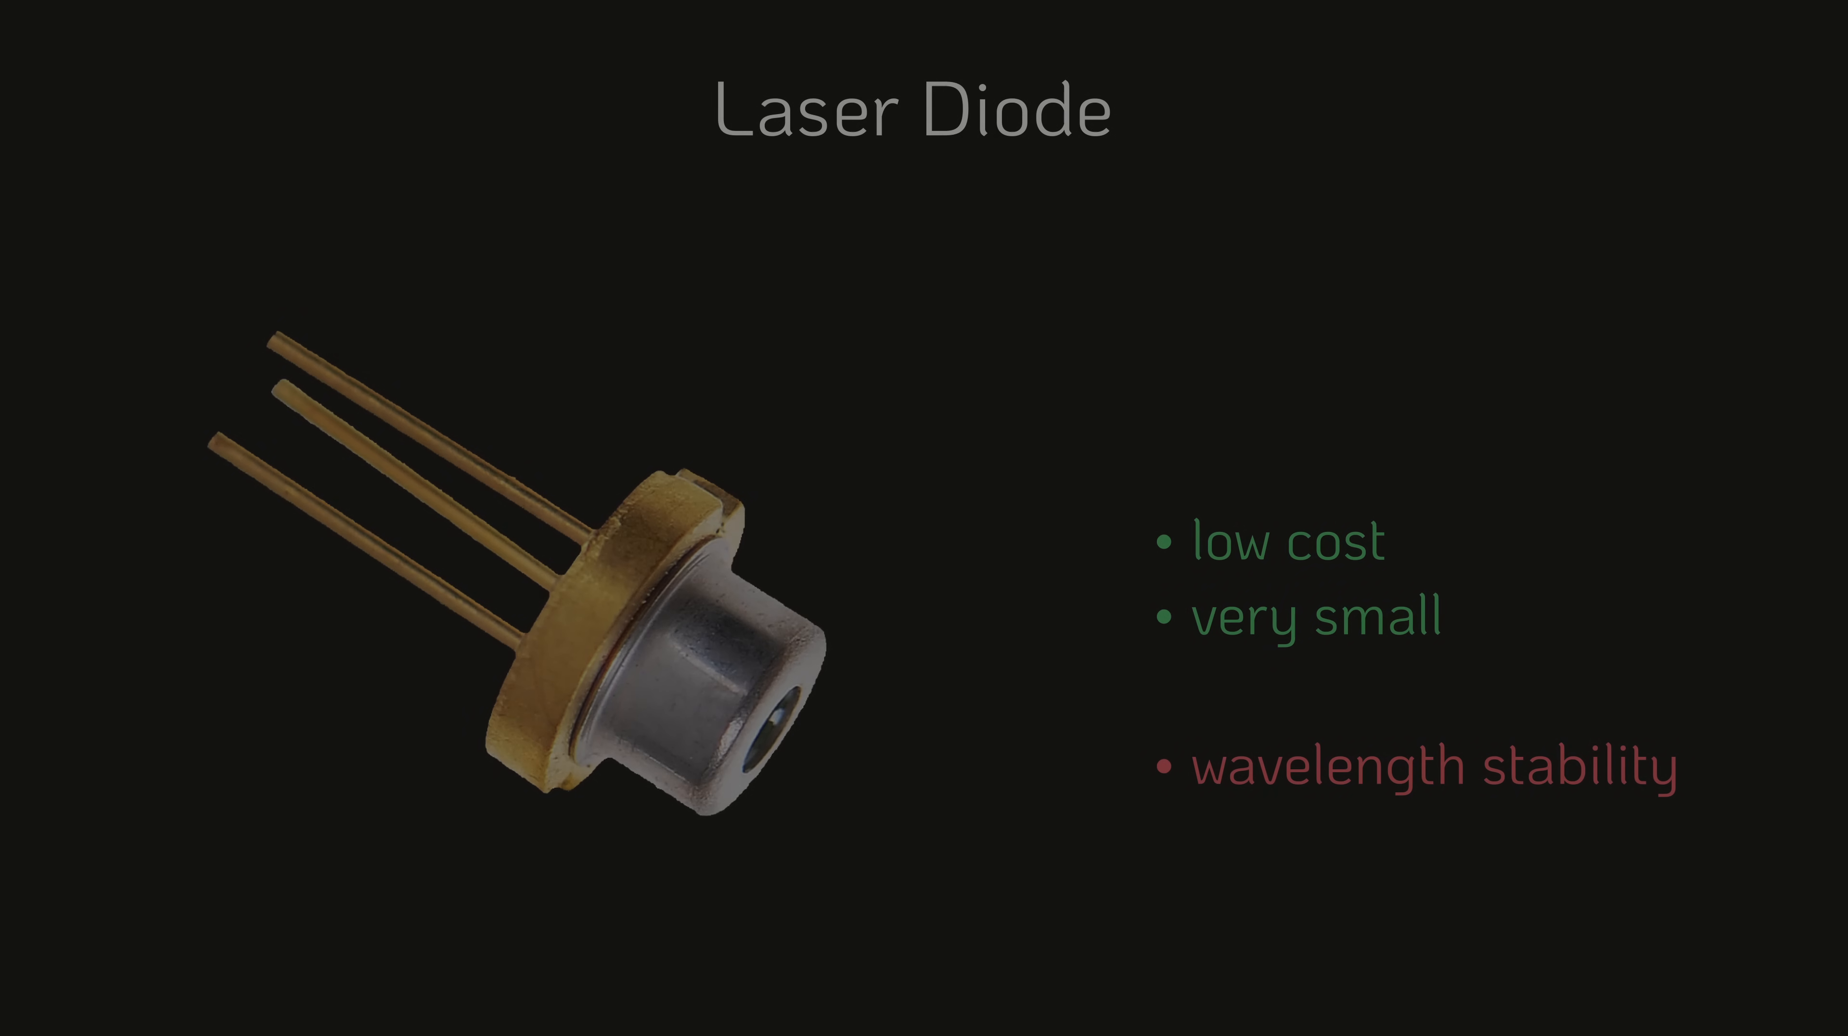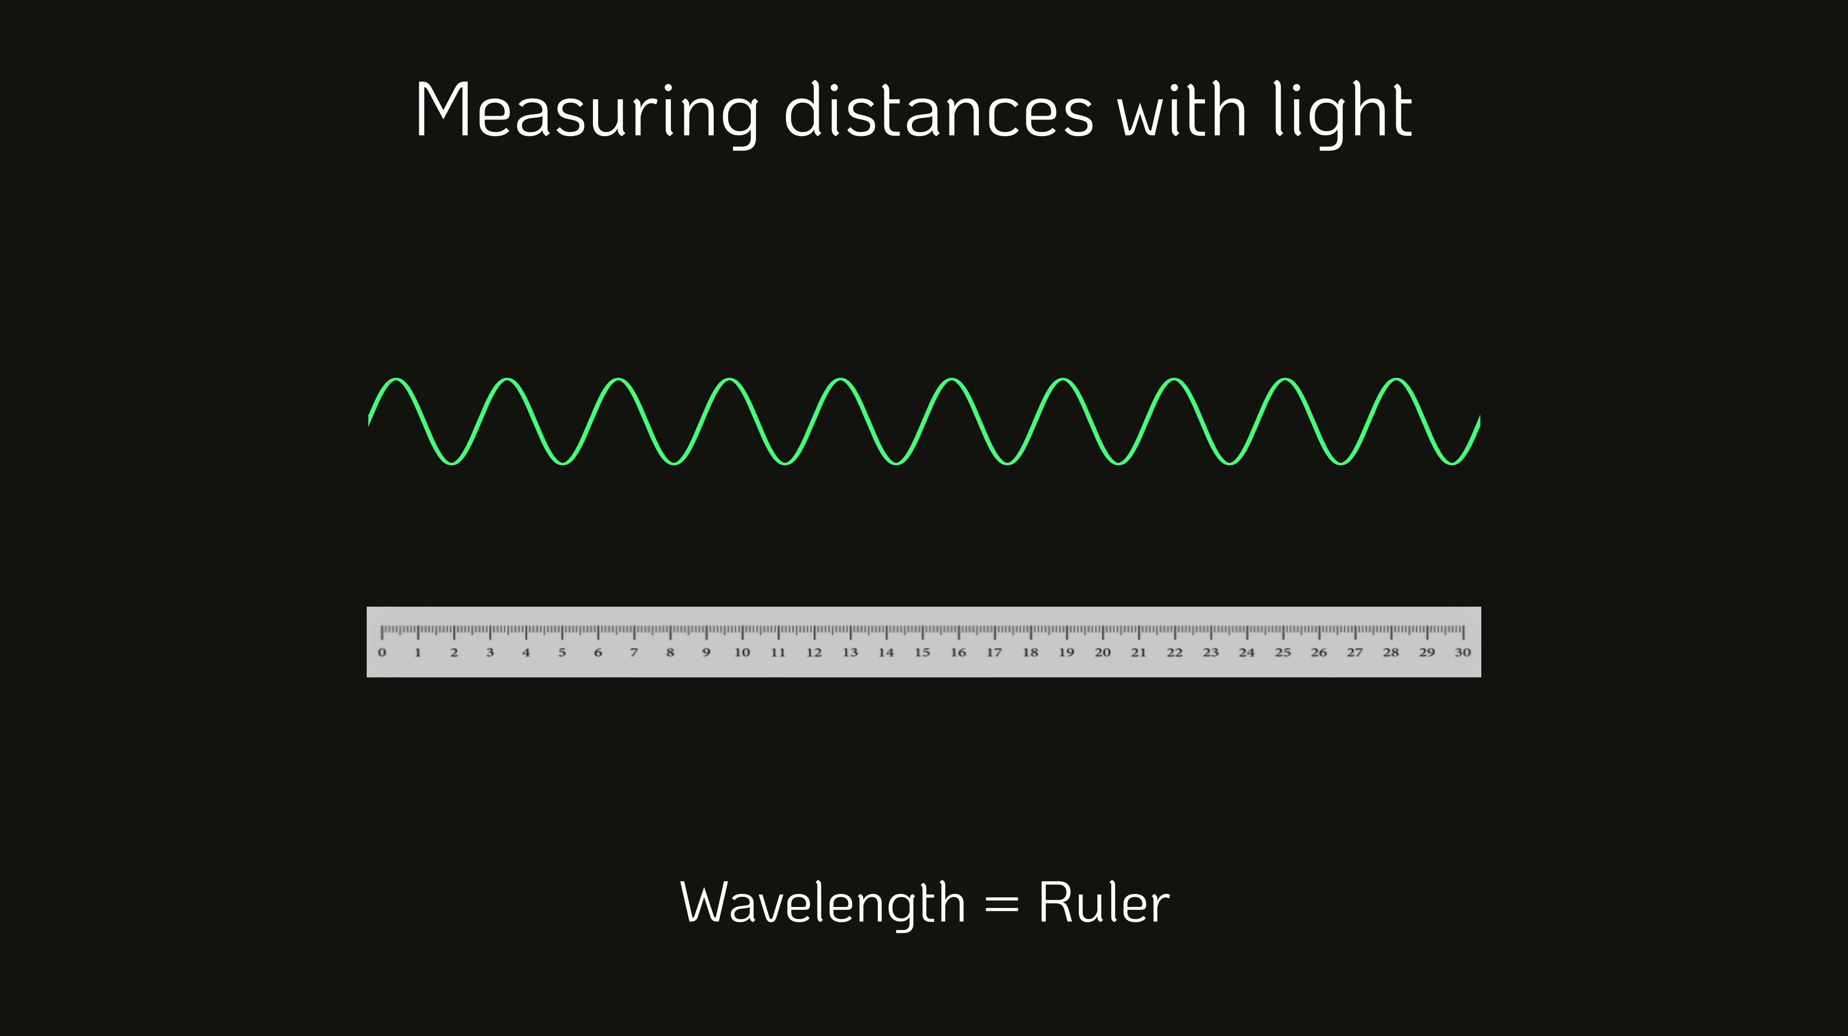To recap, the laser diode is used in the interferometer because it is low cost and very compact. However, unlike alternatives such as helium neon lasers, laser diodes do not inherently produce light with a stable wavelength. This presents a challenge since in an interferometer, the wavelength acts as the ruler used to measure distances. And a ruler, no matter how finely marked, is useless if its length keeps changing unpredictably.